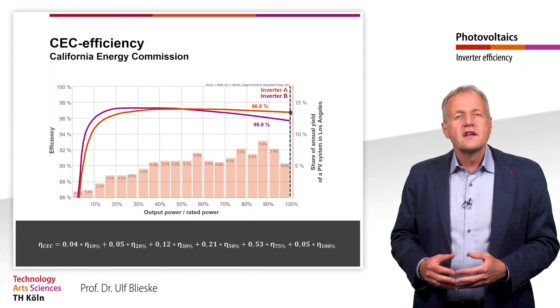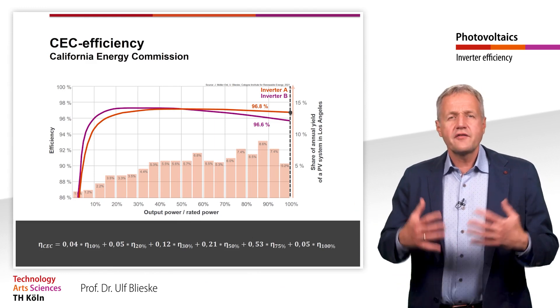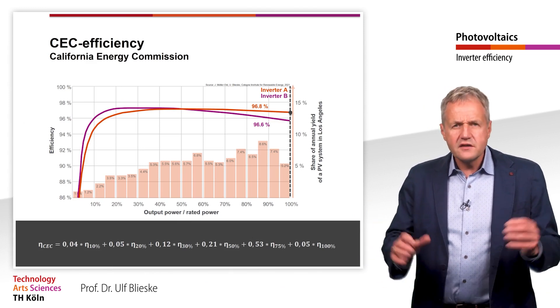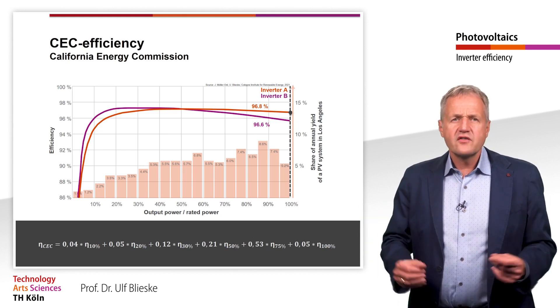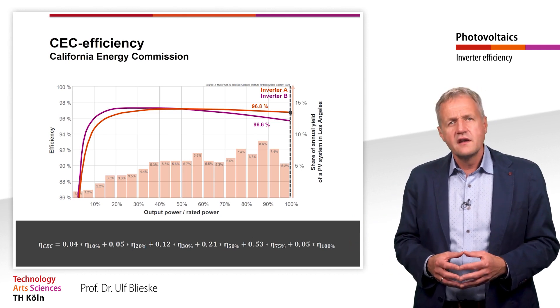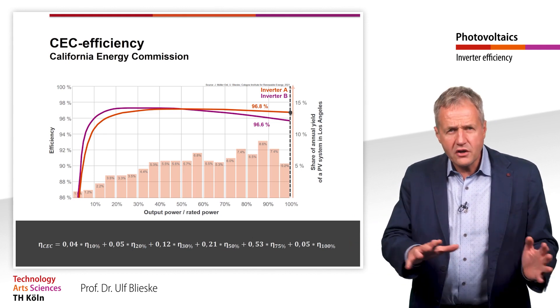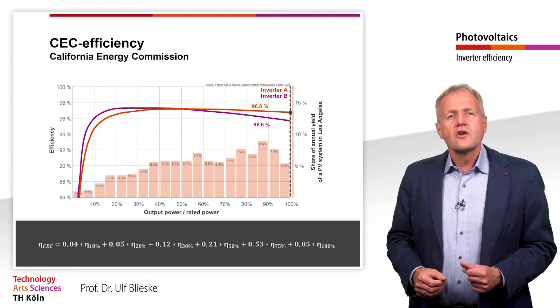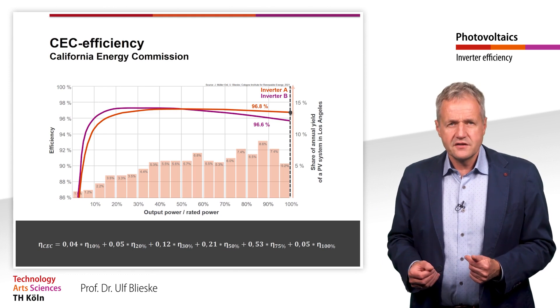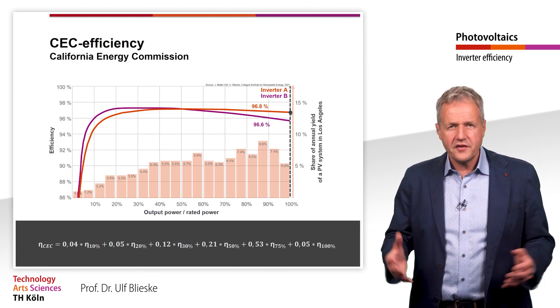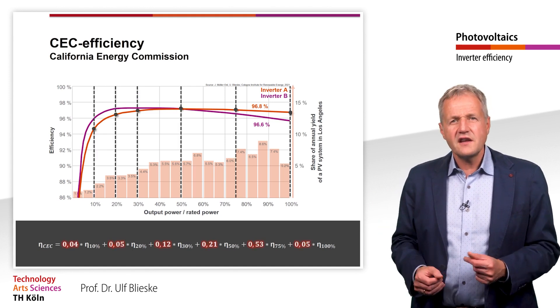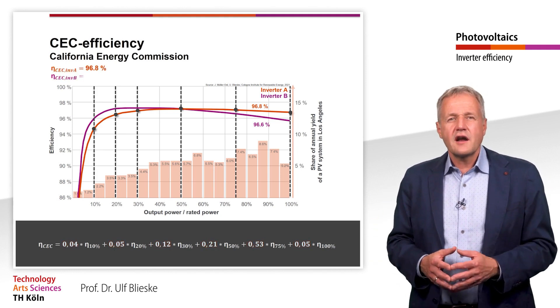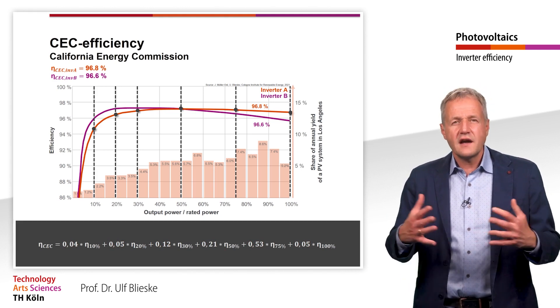For areas with high irradiation, there is another weighted efficiency — the so-called Californian efficiency. Shown here is the energy share of the various outputs in the annual yield for a plant in Los Angeles, a place where higher irradiation can be expected for most of the year. Here the efficiency in the lower partial load range plays only a subordinate role, while higher outputs contribute significantly more to the annual energy yield. This is also reflected in the weighted factors of the Californian efficiency, where the efficiency at 75% of the nominal power receives the highest weighting. For our two inverters, the Californian efficiency values are 96.8% and 96.6%.